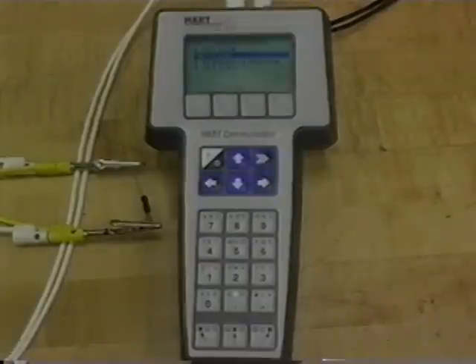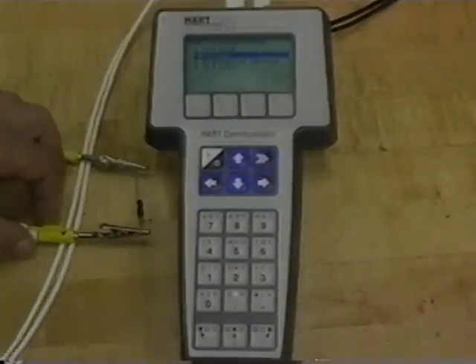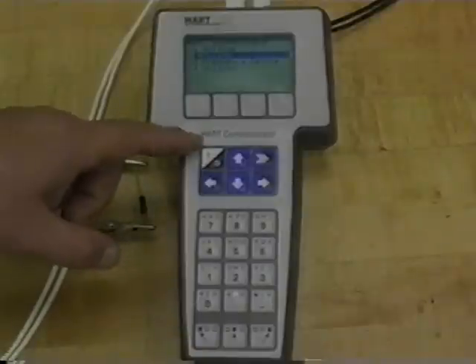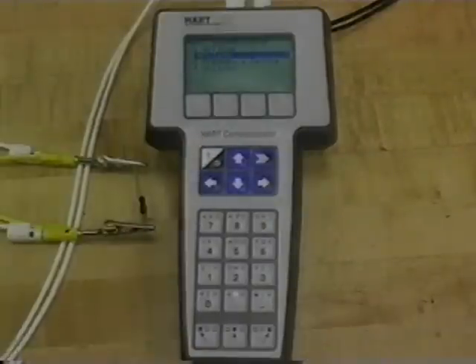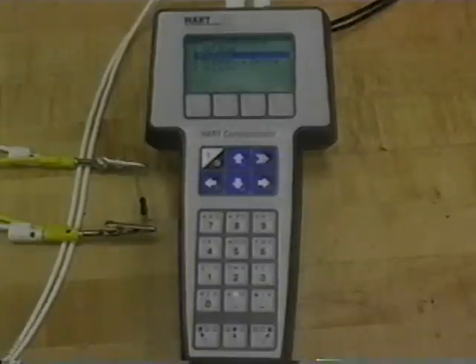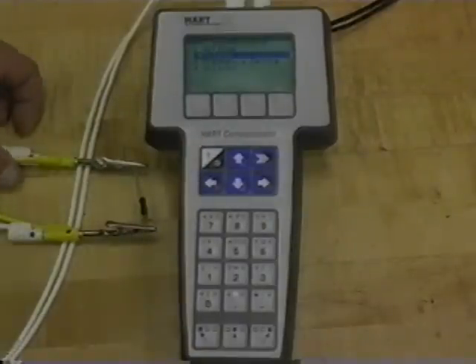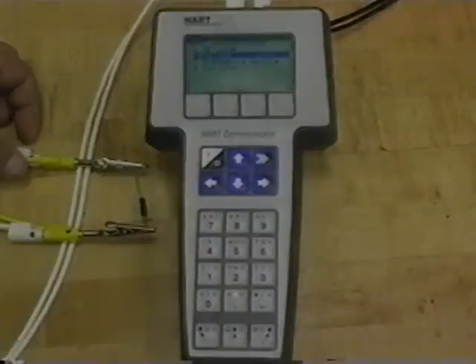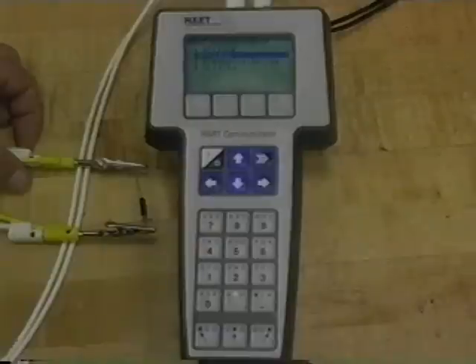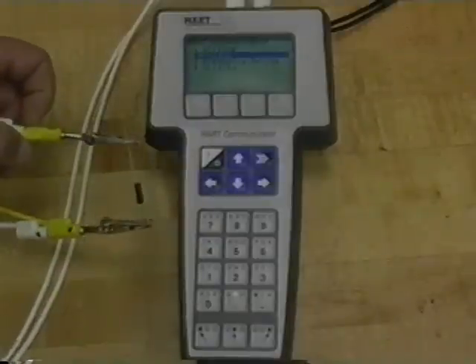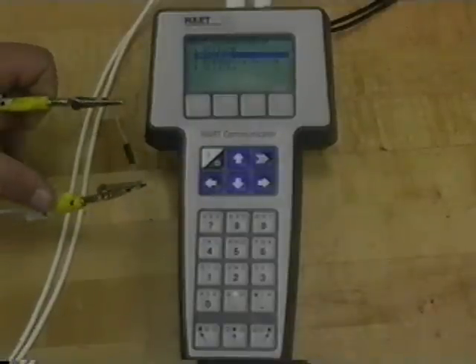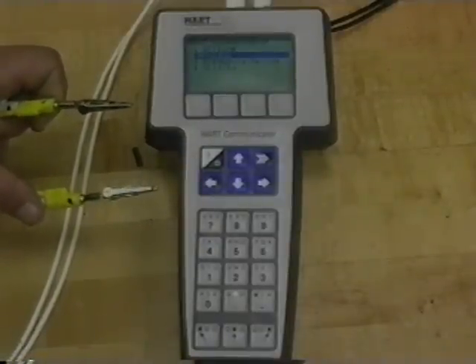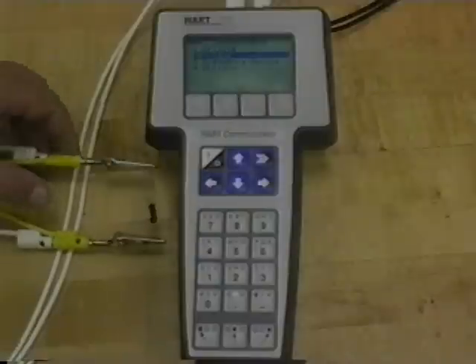The next step is to calibrate the transmitter itself. The transmitter is a smart transmitter using the HART protocol, so we need a HART communicator to do so. The HART protocol is a digital signal superimposed on top of the standard analog 4 to 20 milliamp signal. So in order to allow communications, we need this 250 ohm resistor in series.